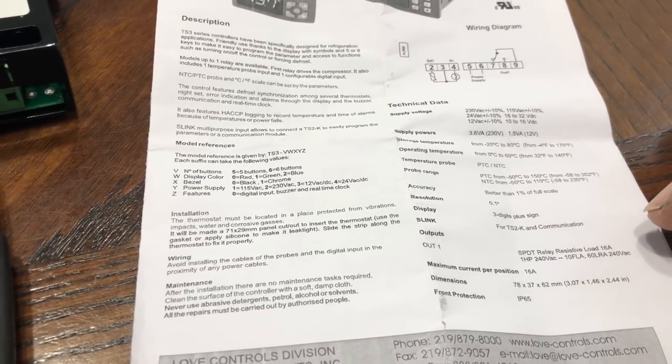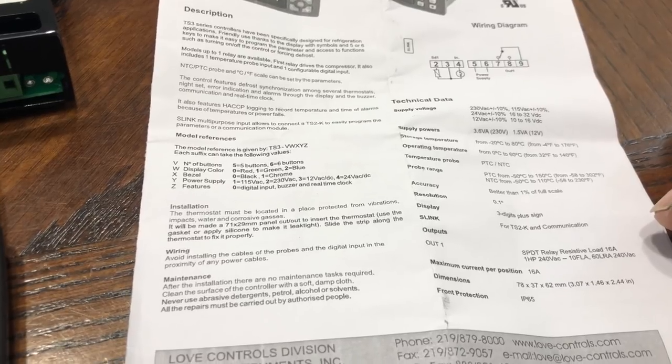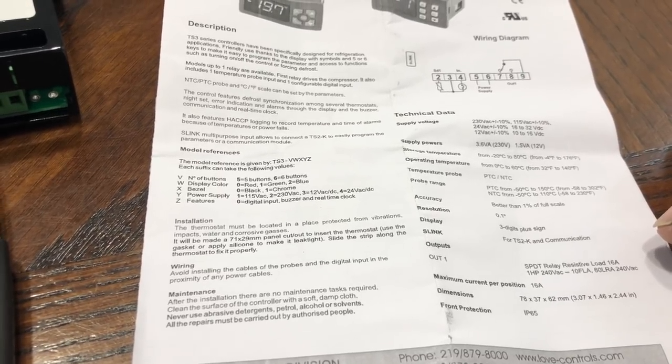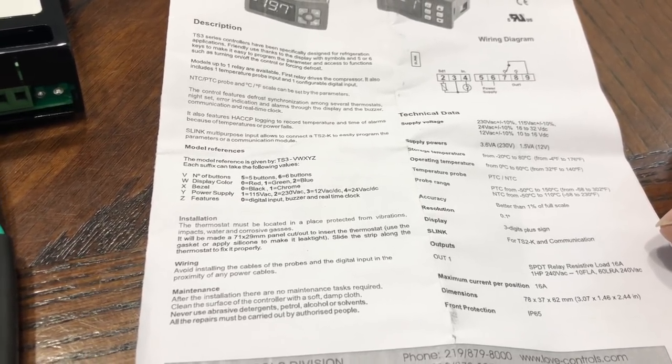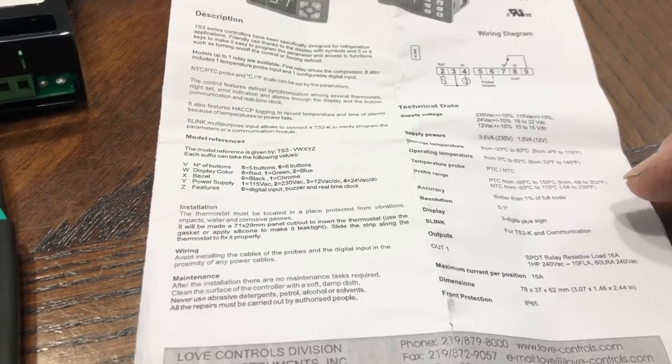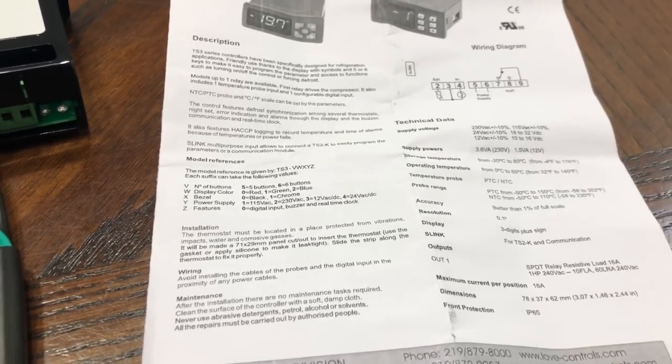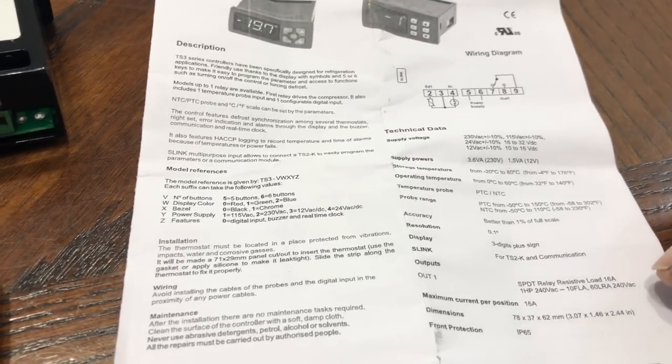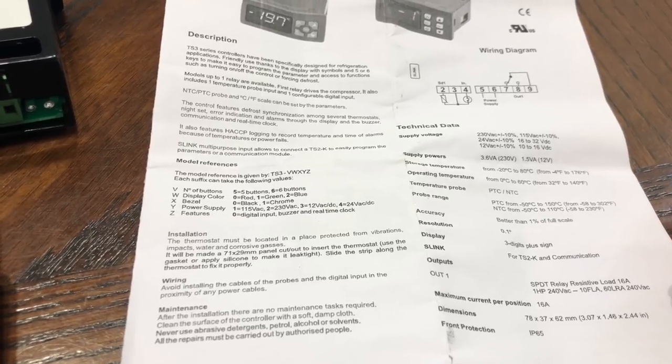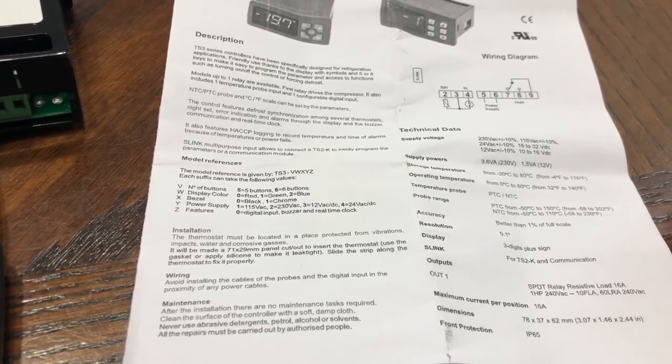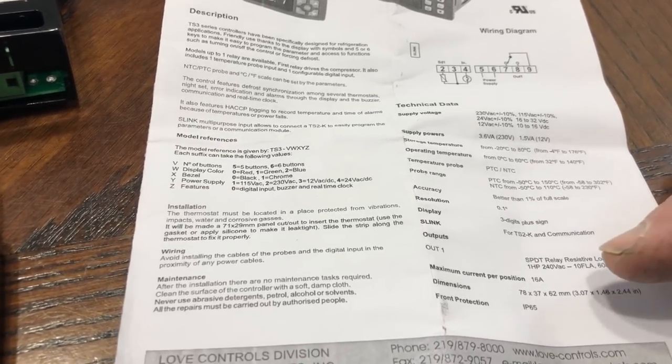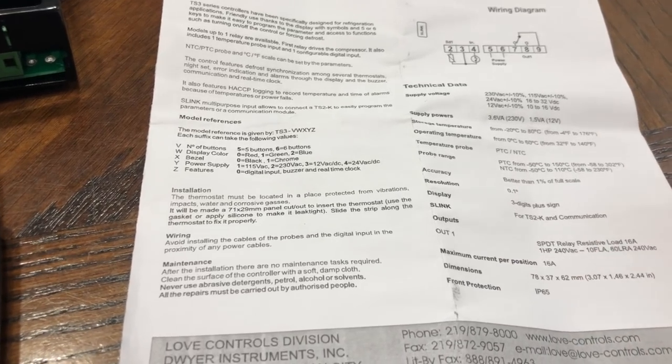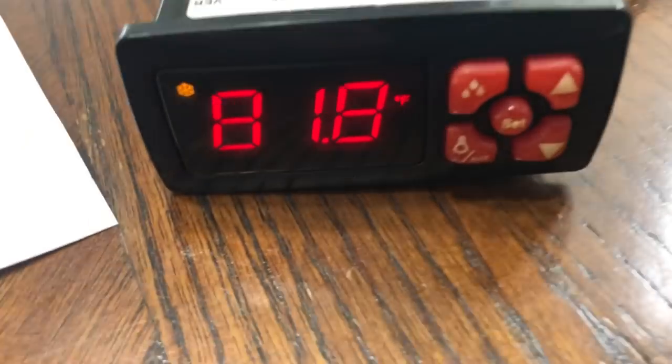The output is good. One horsepower says 16 amps, one horsepower 240 volts, and 10 amps, 60 lock rotor amps. Maximum current per position 16 amps. This little control will do a ton of things right here.